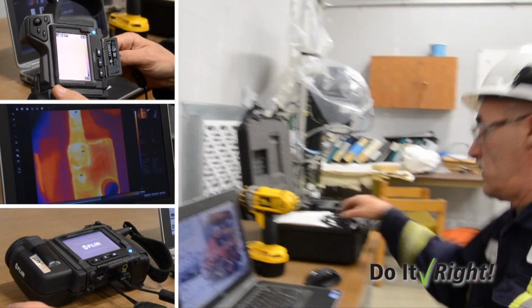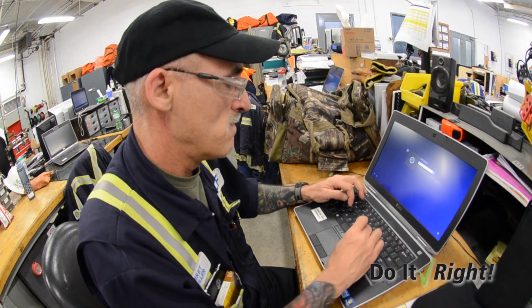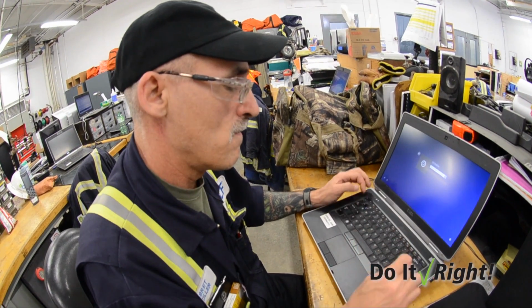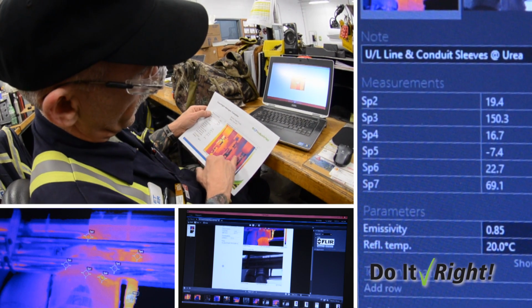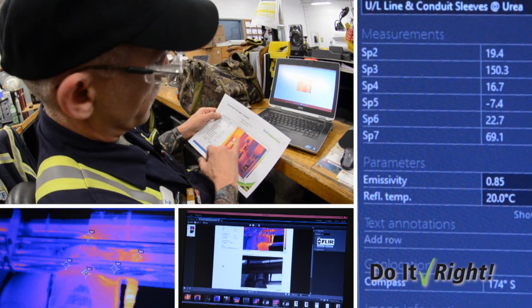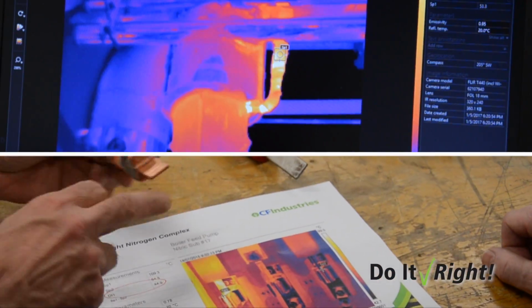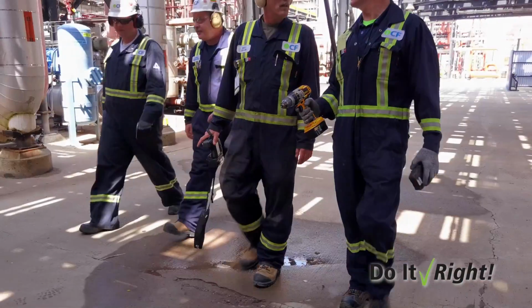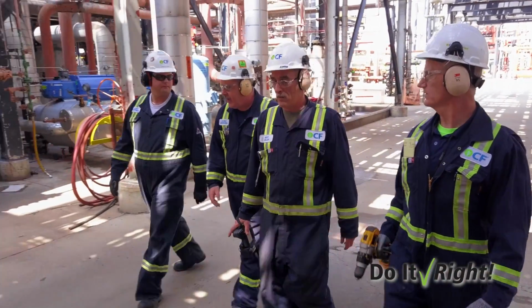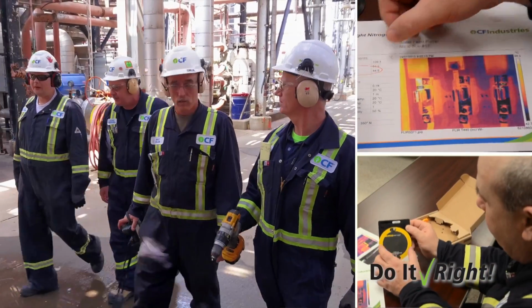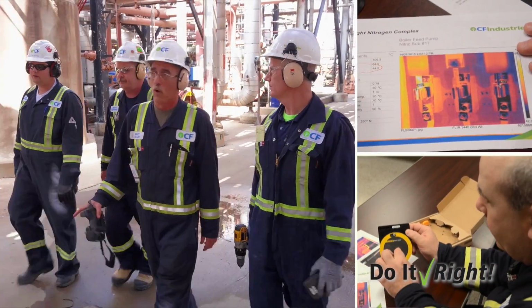With the IR camera, you're looking for a difference in temperature. 2 or 3 degrees difference is a big deal at high voltages. When you see it on infrared, it does not take long to show you a hot spot. Hot spots are where you're getting a small amount of arcing and contact and deterioration in the system. It took us about 3 years to do the complete install. The 200 some windows were done.